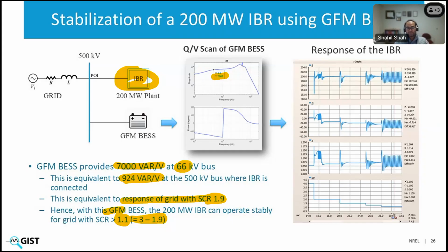So to confirm this finding, we connected this bus and ran time domain simulations. And here is the plant, which is supplying 200 megawatt of output on the right. We start reducing the SCR of the grid from 4 to 2 to 1.5. It remains stable at 1.5. We reduce it to 1.25. It still remains stable. And only when it hits 1.1 does it become unstable.